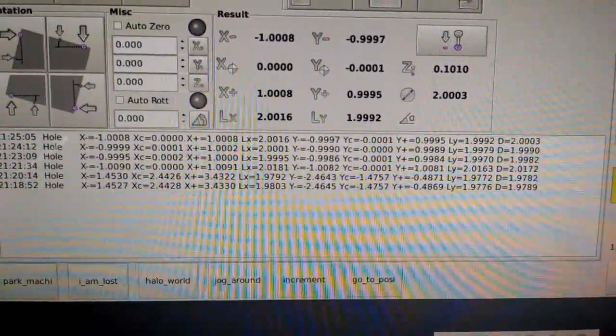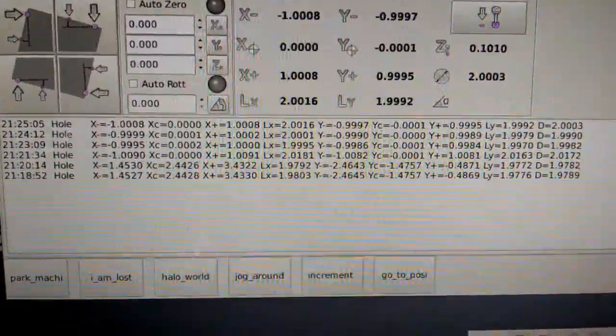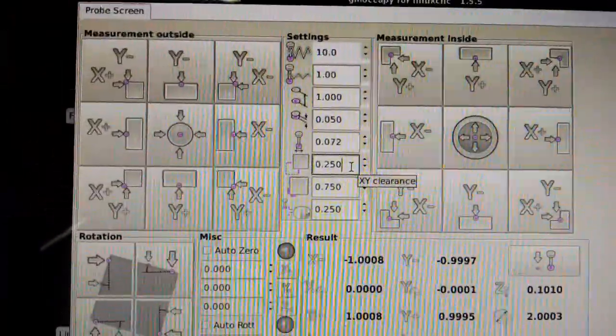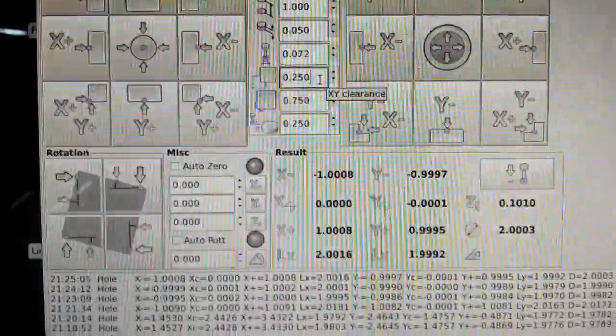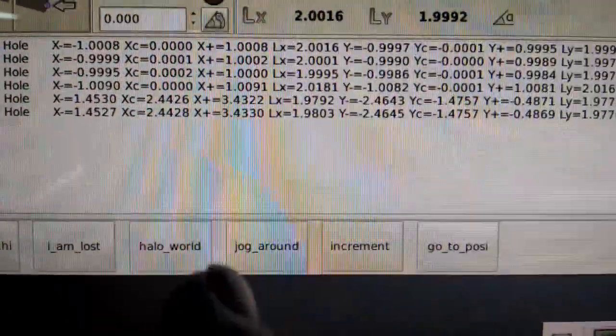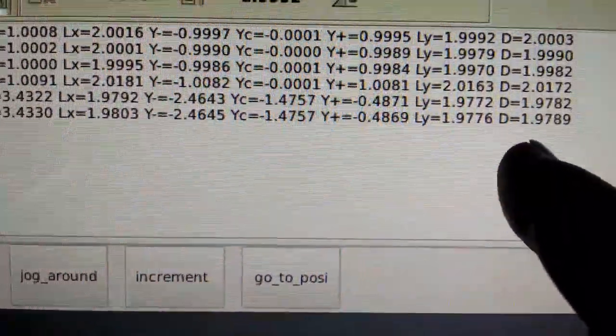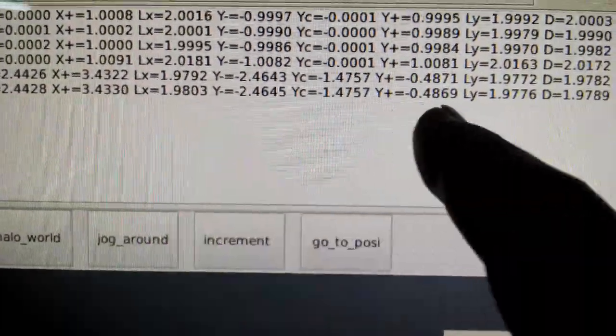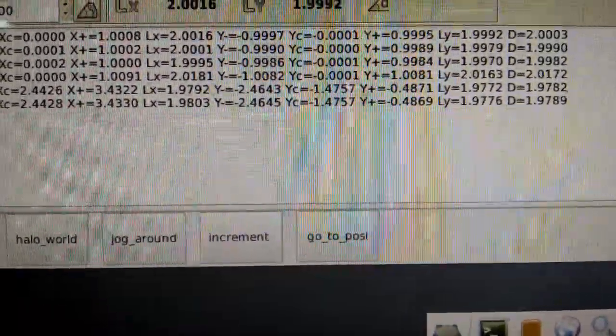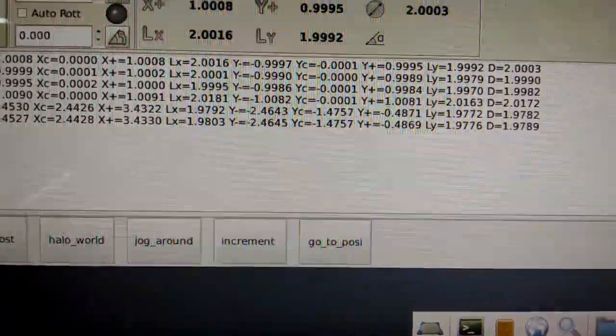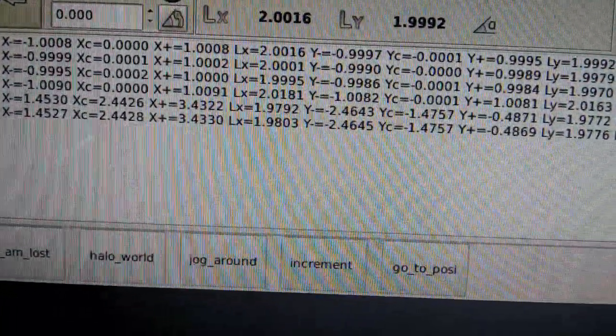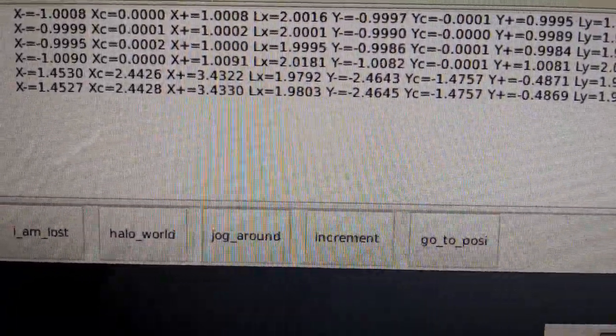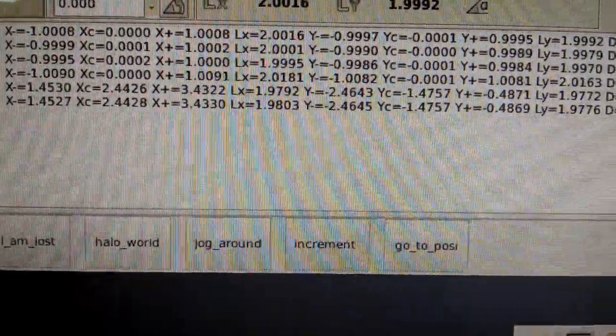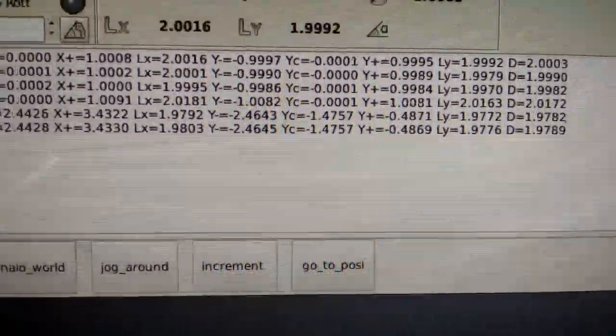Okay, so this shows some results from probing multiple times, and during the times that I've been probing here, I've been changing the diameter of the probe tip. That 0.072 is what I have now. The reason I've been doing that is, if you look here, you can look at the LX, the LY, and the D. And all three of them should be 2 inches exactly. The hole that I'm probing, which is this, is 2.000 inches, as I can measure it with my calipers. It's 2 inches exact. So those numbers should all be 2 inches.